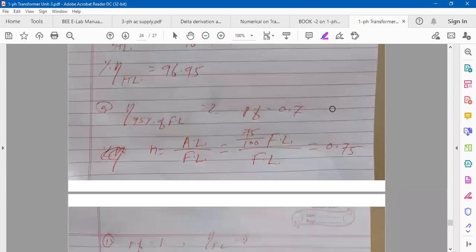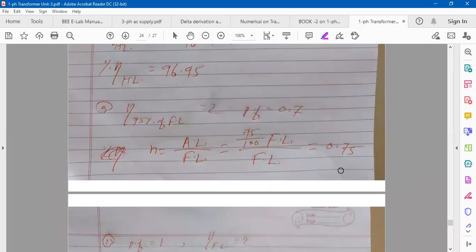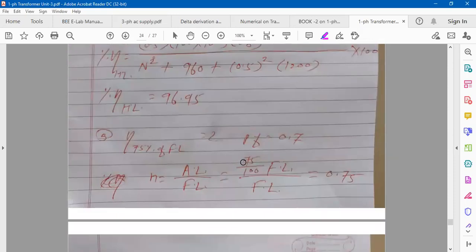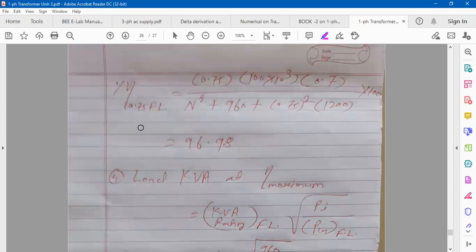For efficiency at 75% of full load, power factor 0.7: N = 75% of full load / full load = 0.75. Put N = 0.75, KVA = 100 × 10³, cosφ = 0.7, divided by same parameter plus iron loss plus N² times full load copper loss, into 100. You will get approximately 96.98%.